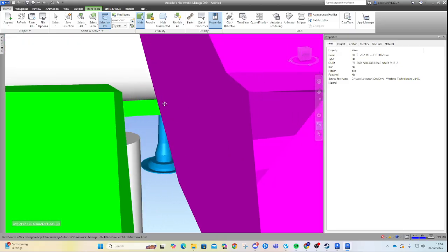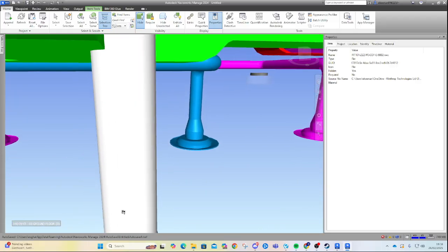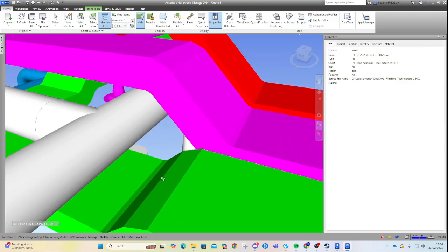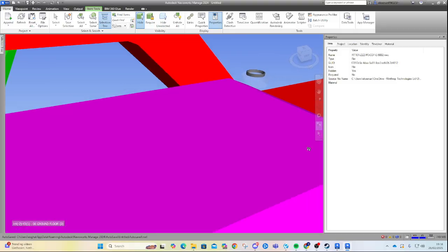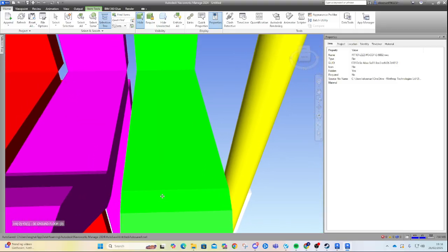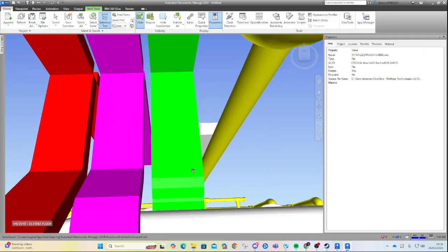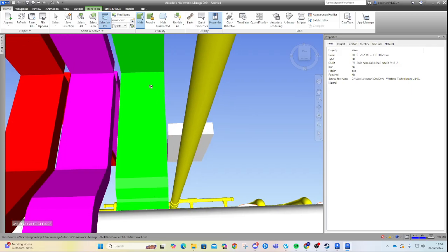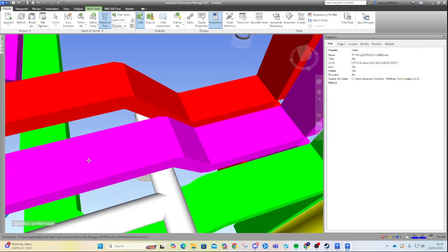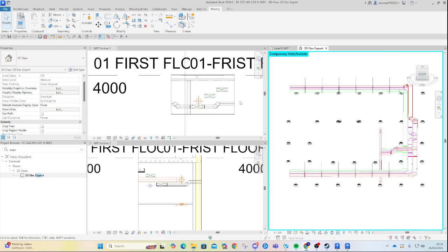So this is something that we didn't notice. Well, I missed, because this pipe comes up, so that duct does. To solve this clash, we just have to increase the space between here and here and tighten up there, and we should miss it. So it's a relatively easy clash to solve because we just have to pull this across. Okay, well let's solve that one anyway.